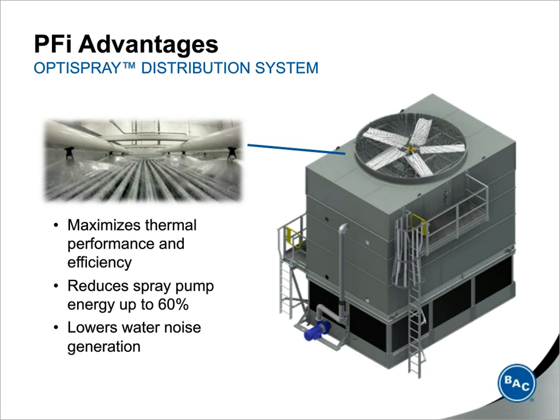Now, because of the optimized spray and airflow, this technology also can reduce the amount of recirculating water in the system, so the falling water produces lower sound levels than traditional counterflow designs. And again, I just want to reiterate, crossflow units still offer greater efficiency, access for maintainability and reliability because of the accessibility that you have. They do offer all those benefits over counterflow units. However, this advanced heat transfer technology and the new spray system really provide great benefits over traditional counterflow designs, and really do make great replacements, and again are excellent for situations where you need to save space.